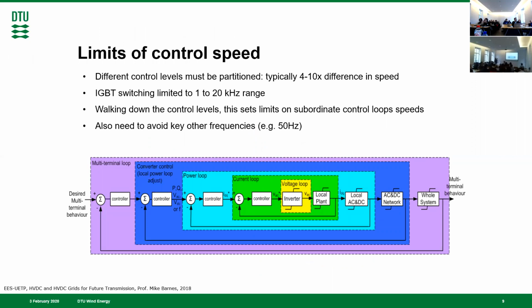So talking a little about the control of that, this is a picture I borrowed from another lecture. It's not really about the power electronics inside the wind turbine, but the principles are very similar. So we have the different cascaded controls and their control speed, basically dictated by the physics of the power electronics, the IGBT switching devices, which switch with a very high frequency. You typically have to design your control loops so the outer loops are slower.